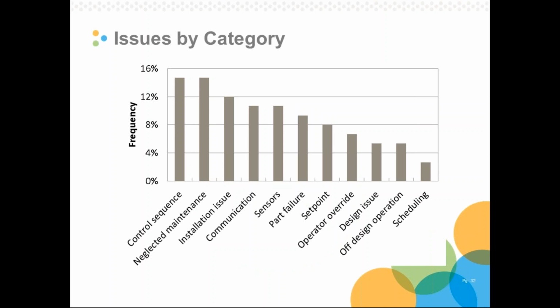We did a lot of different categorizations. You can find more in our final report, but I want to briefly touch on this one. We put everything into these main categories, 11 main categories, to try to describe the kinds of issues we found. So most commonly we found issues with control sequences. This is incomplete control sequences. This is missing control sequences, for example, no cooling mode. We found neglected maintenance. Again, returning to our fouled air filters. These don't have direct energy penalties, but according to best practices, we should be regularly changing our air filters.